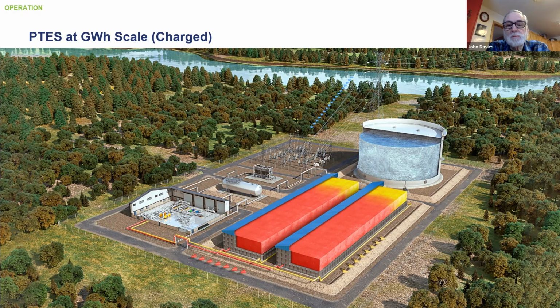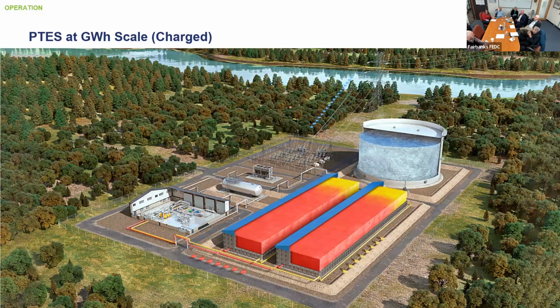Yeah, those are great questions. So what's drawn there, what looks like a solid block of ice, is not actually a solid block of ice. Inside that tank are a series of coils of tubing. The CO2 flows inside the tubes and the ice forms on the outside of the tubes. We don't go to 100% ice like this shows, it's really about 70% ice. So even at the fully charged condition, there's still gaps between the ice layer on one tube and the adjacent tube. That's what allows us to not break stuff.